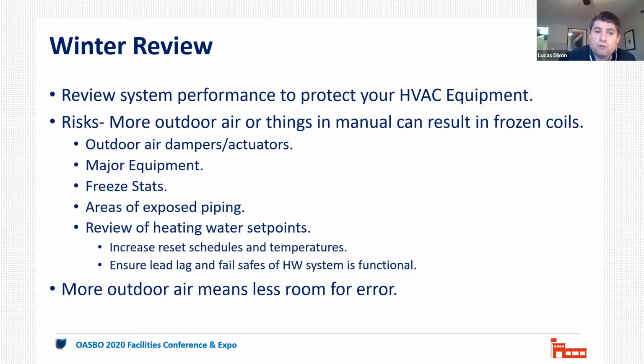And then Matt, you brought up some really important points about how we also should look at our heating water set points. So why don't you talk a little bit more about that? So the traditional reset schedule for heating water systems is relative to either space load and or outside air temperatures, but this assumes you're at design ventilation conditions. This winter, in response to COVID, your systems are going to be asked to exceed their normal design ventilation parameters. Therefore, it may be time to look at your reset schedules and analyze whether you need to actually raise those reset schedules so that hotter hot water is available.